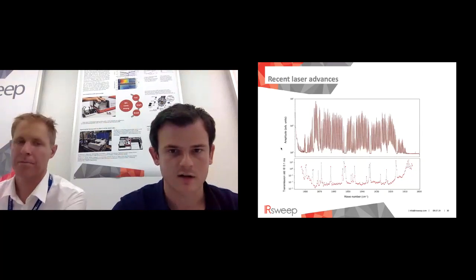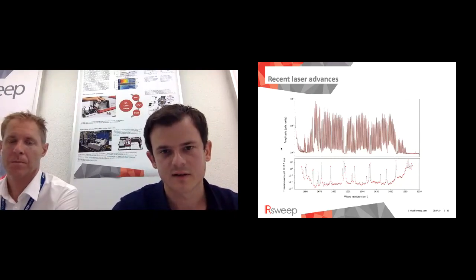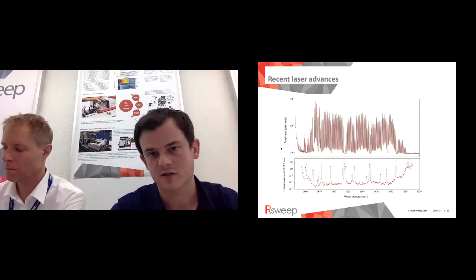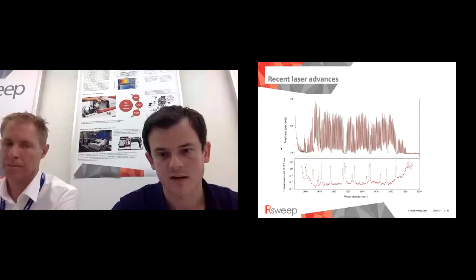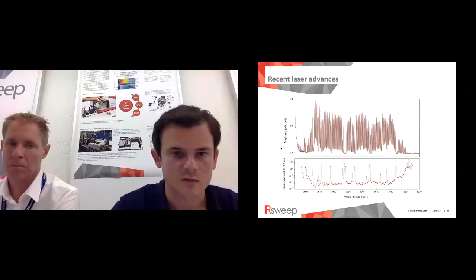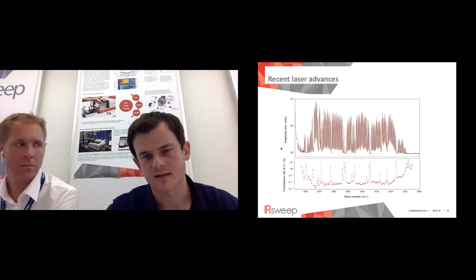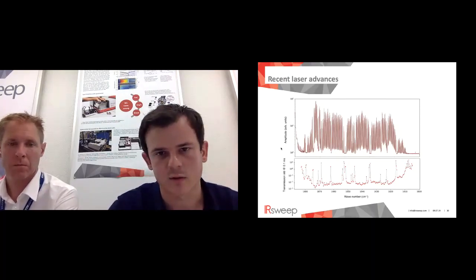One question that we get very often is the intensity distribution of the laser, and I want to address this in the end now very proactively. Does the laser have to have minima in the spectrum? No, it doesn't. This is an example of a 6-micron laser that's used for protein dynamics measurements usually, and there you see a relatively flat spectrum. You see certain minima where the intensity is almost 0, and in the bottom panel you see that this is where water lines are. So you have no laser light, but this overlaps very nicely with the water absorption lines.